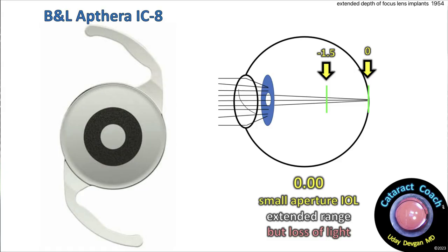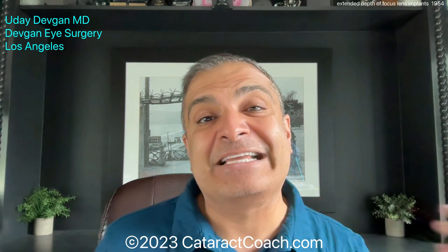We have the Bausch & Lomb Apthera IC8. This was originally developed by a company called AcuFocus, who planned on putting small donut-shaped rings inside the corneas of patients — like a LASIK flap, put the ring down, close the flap, and let it heal up, giving a wider range via the pinhole effect. It was meant for the non-dominant eye of a presbyopic patient around age 50. It worked pretty well, but some patients' corneas didn't tolerate it. So the company had a brilliant idea: put this into an intraocular lens, an IOL, where it's sequestered from the eye, the cornea is happy and untouched — and that's how the IC8 lens was born.